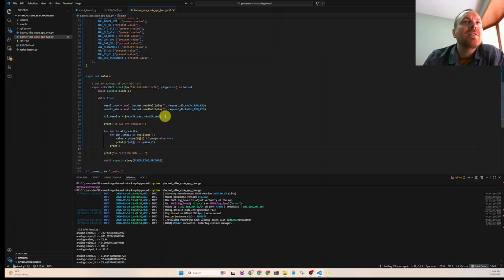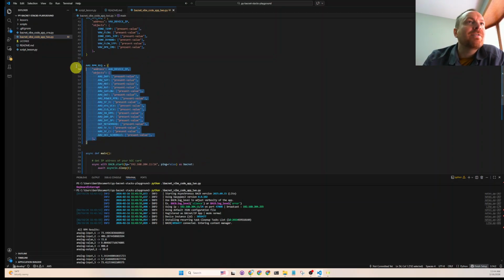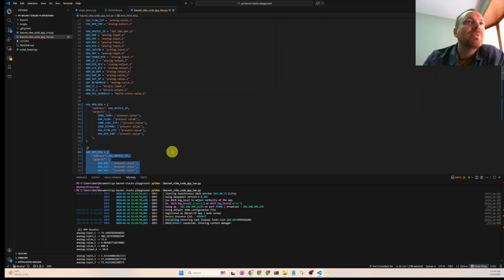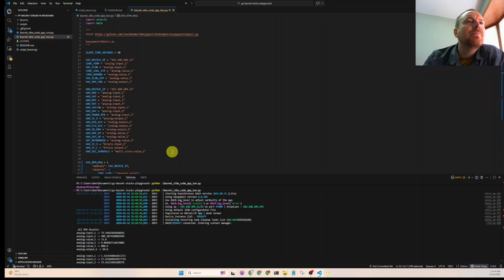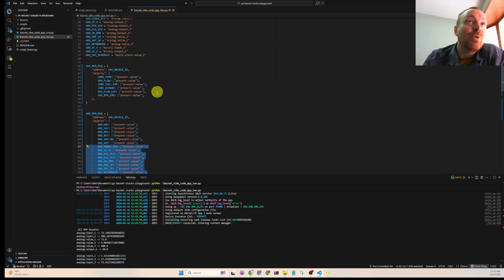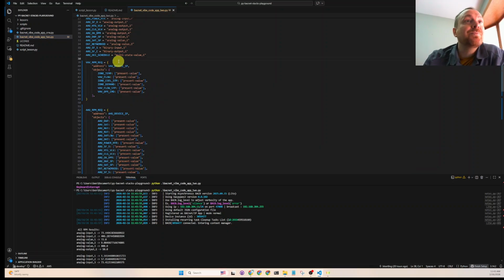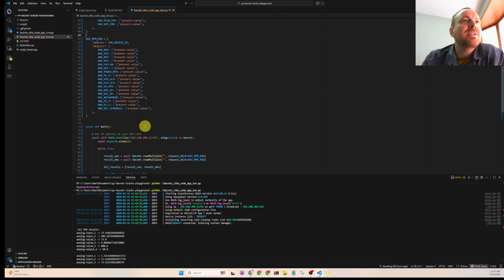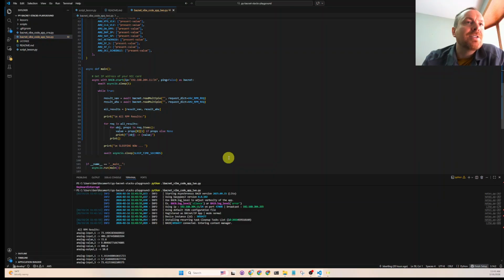Then we're passing in our NIC card information here. A little bit of fat fingering going on with our BACnet scan tool. But this is probably the right way to do it. Rather than, if you do an object discovery, saving that data to a CSV file and then editing the CSV file as needed, because you don't need half the points in the building automation system, just only scrape what you need. That keeps the BACnet network healthy, because there's not a ton of data flying around.